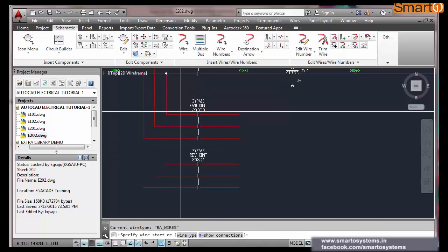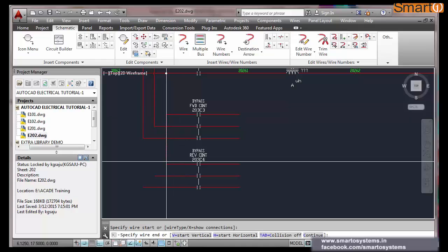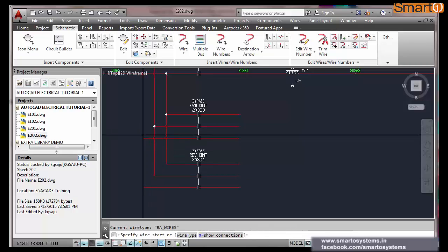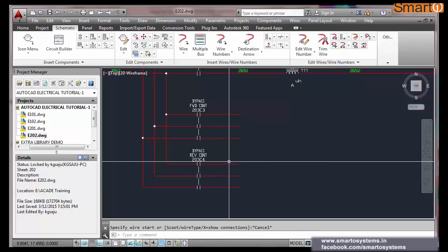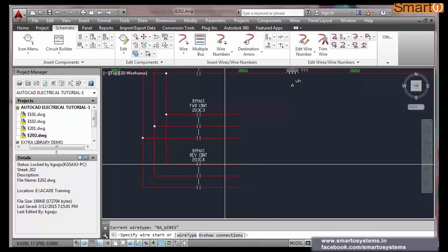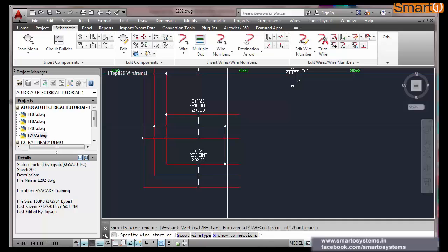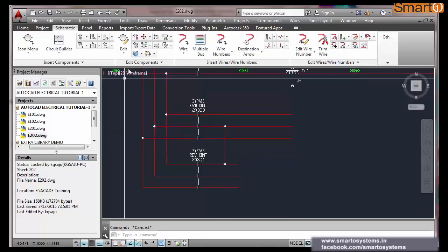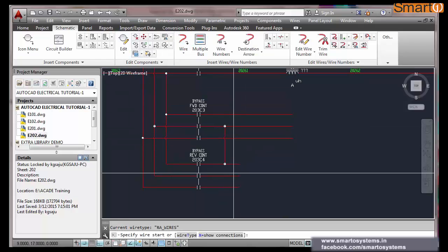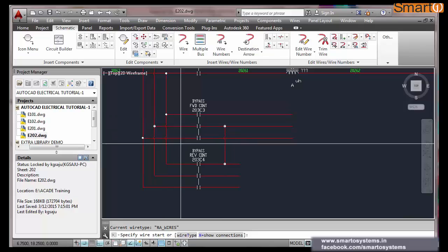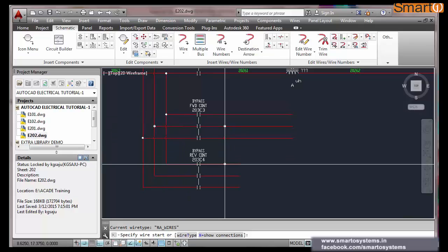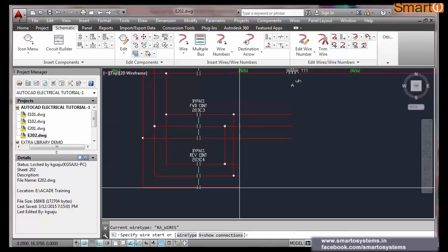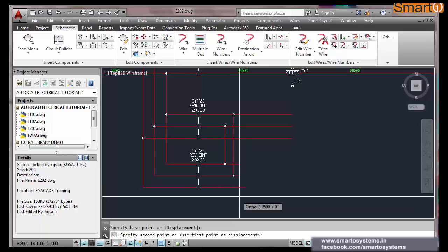Now in the reverse, what you have to do is, this is R1, this is Y1, this is B. And in RDOL case, what we normally do is we swap two phases, reverse two phases, R and here you see R and R, but in this side R is connected to Y and Y gets connected to R and B is as such.